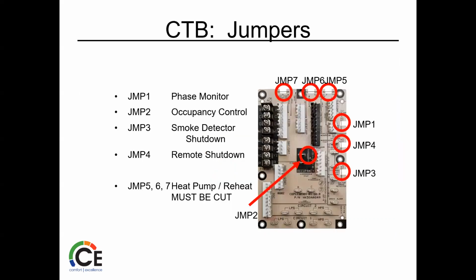So we talked about those jumpers. Obviously, the board is going to come with all of those intact, and you have to know what's cut, what's not cut. Obviously, it's nice to know why it's not cut. The jumper one there on your right, obviously, we're talking if we have a phase monitor, we're going to cut that because obviously we're sending power out of the board. So if we don't, we're blowing a 24-volt fuse. Occupancy control is in the center there if there's some need for that.